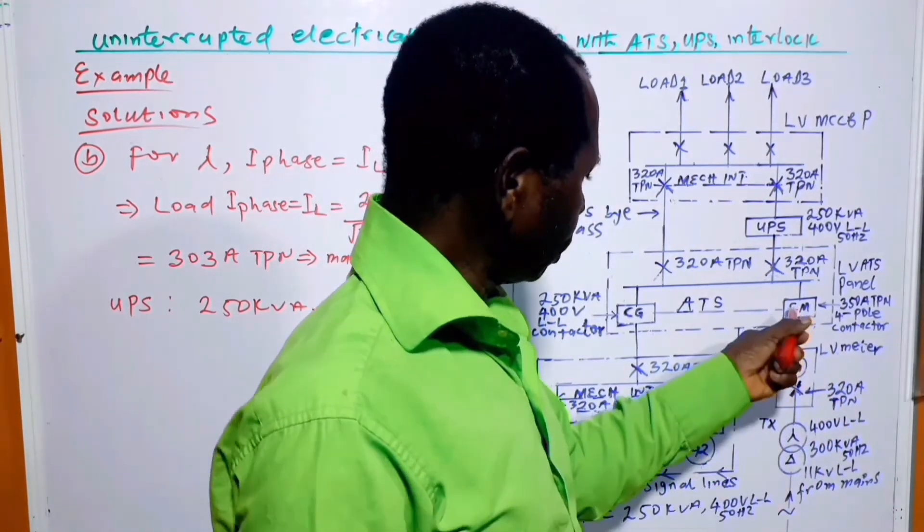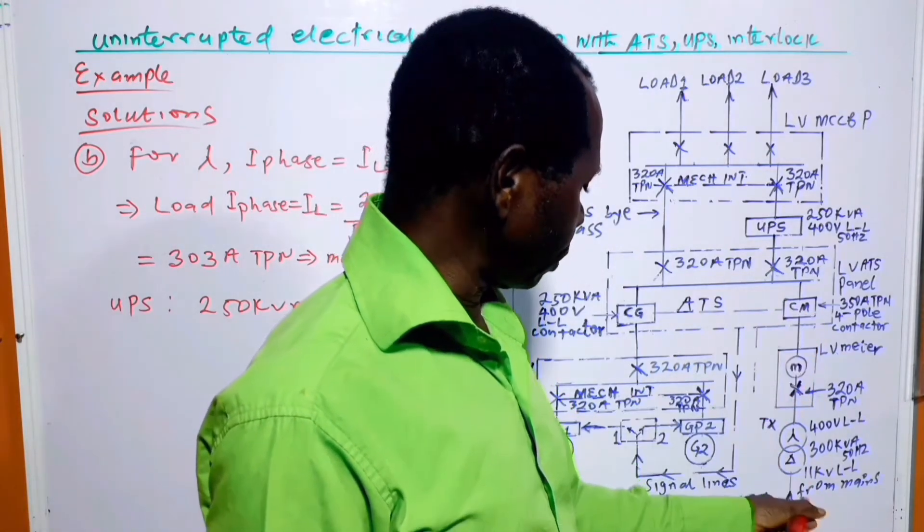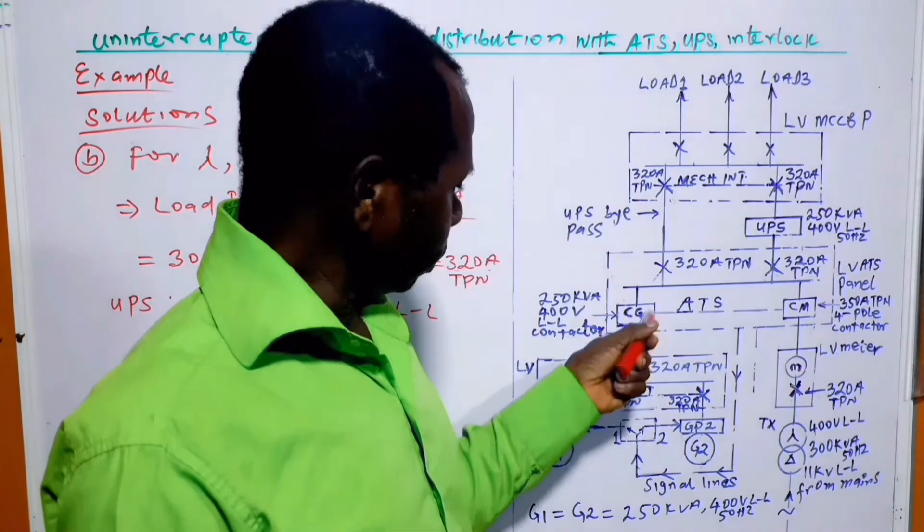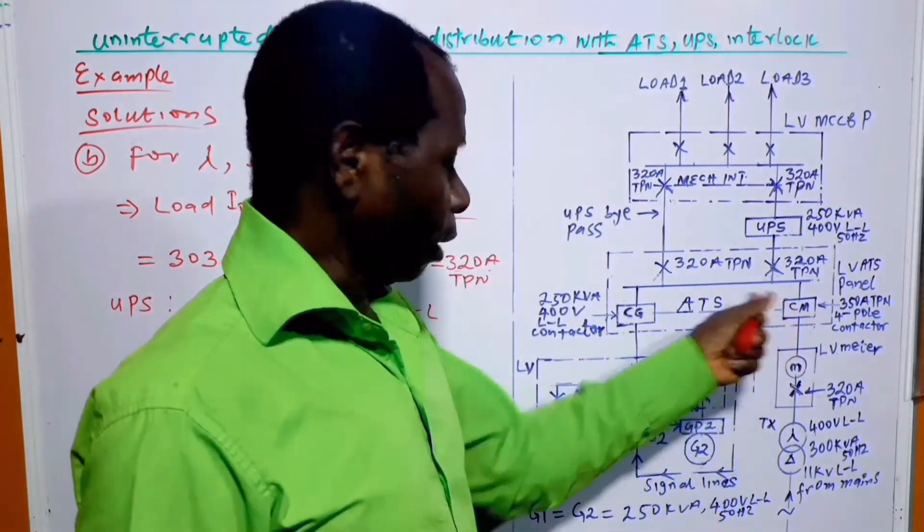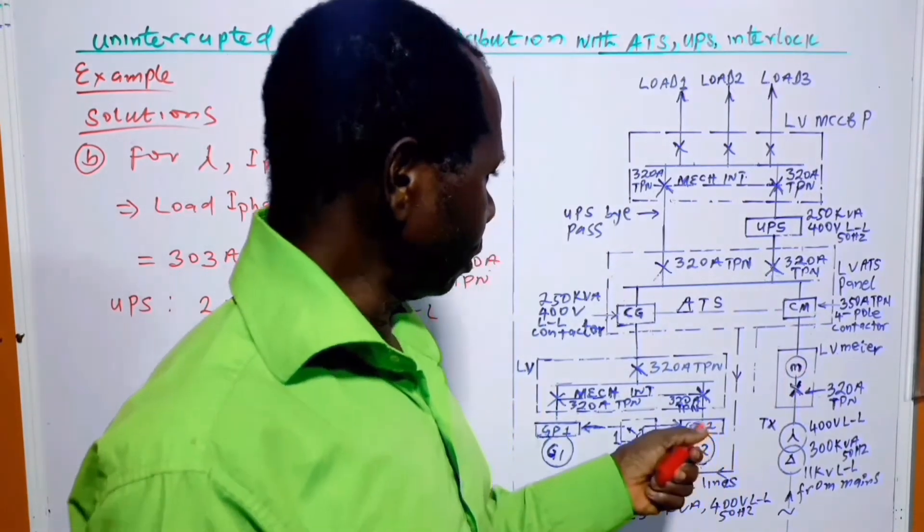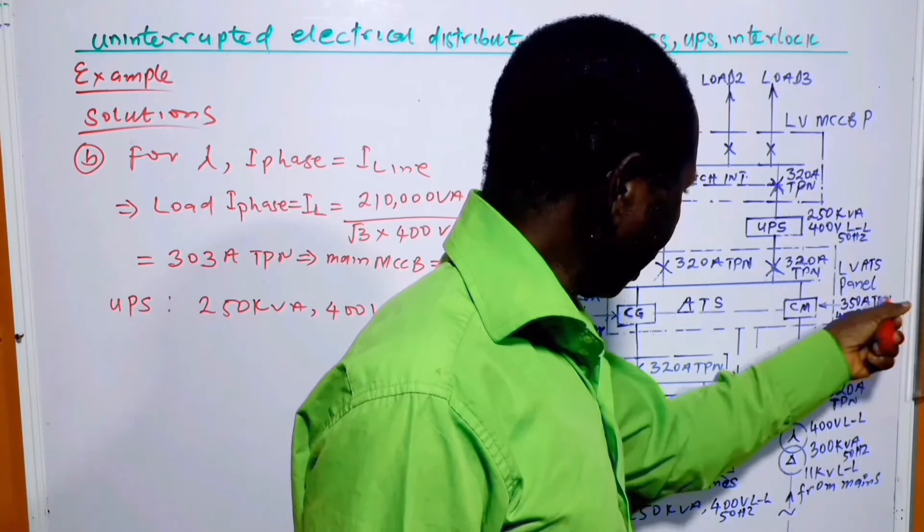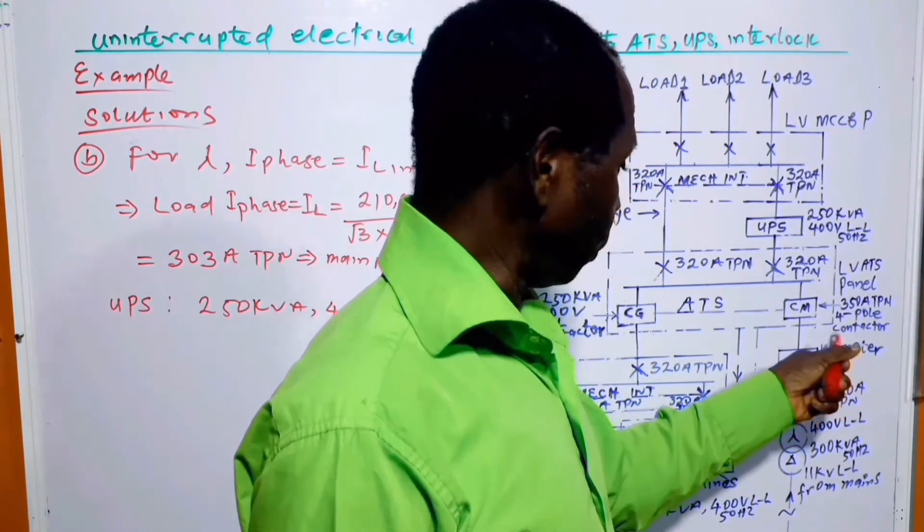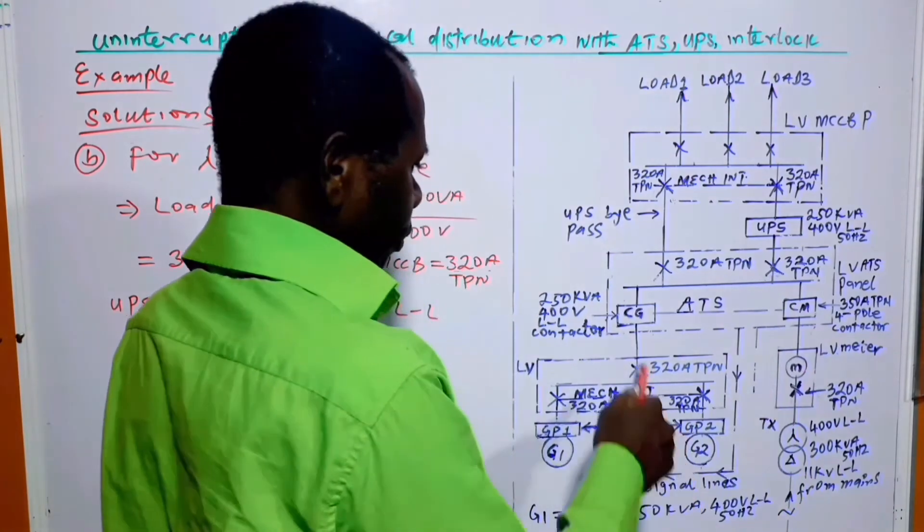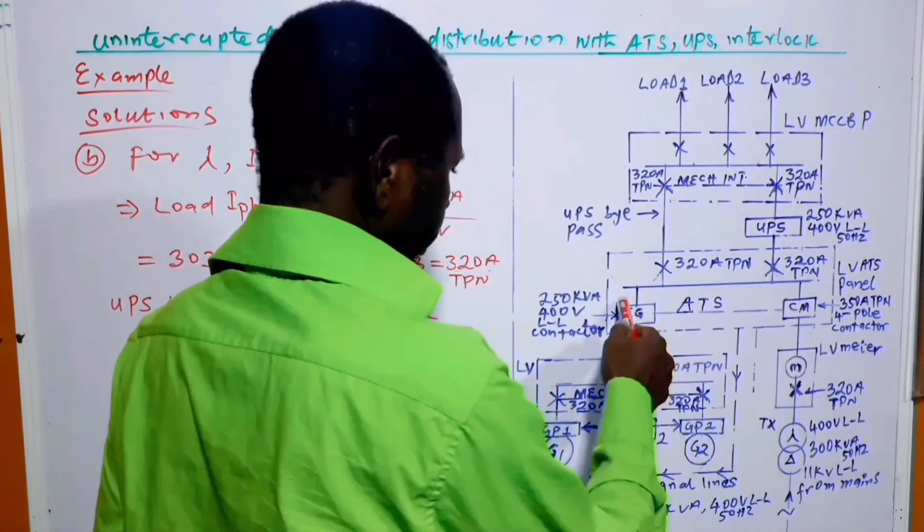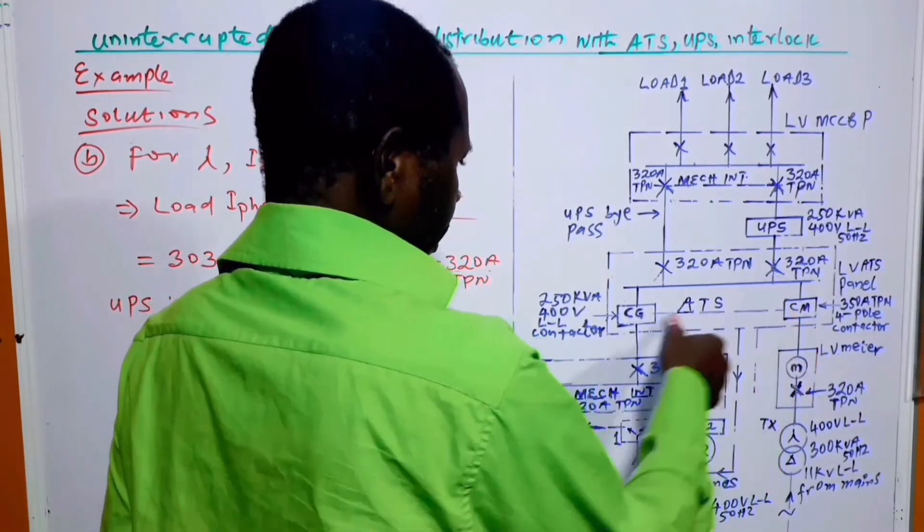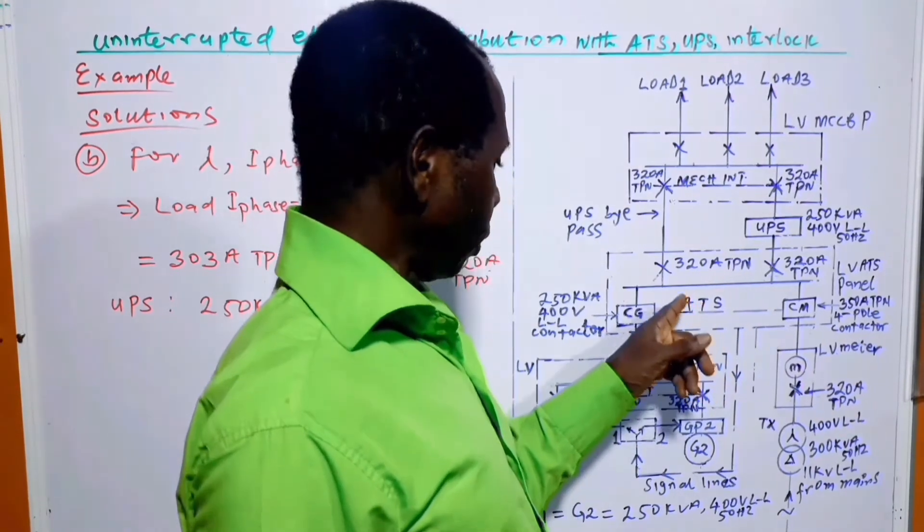From the energy meter we come to the CM, which means contactor for the mains supply. In order to have an automatic transfer switching system, it is easier to use a contactor or we can use a motorized circuit breaker. But in this case I am choosing to use a contactor. The contactor current rating is 350 amp triple phase with neutral or it is 4 pole contactor. Then instead of the conventional MCCBs, we are having two contactors, one from the generator system and the other one from the mains. They are now linked like this.